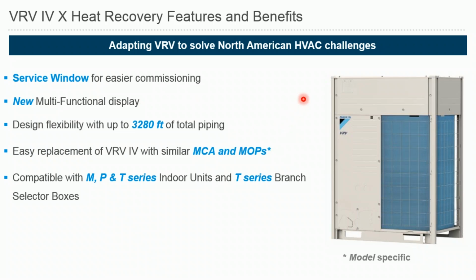Piping capability still stays the same as VRV4. There's not much changing. There's still a lot of flexibility there with 3,280 feet of total piping. From the electrical standpoint, for easier replacements of VRV4 units, your new MCA and MOP levels will be pretty similar to existing models. So if you're planning to switch from VRV4 to VRV4X, that will be an easier change for you. From the indoor unit and branch selector box compatibility standpoint, pretty much everything we have been selling in the North American market will be compatible with VRV4X, so no problems there. And for branch selector boxes, you'll still be able to connect the existing T-Series models to 4X.